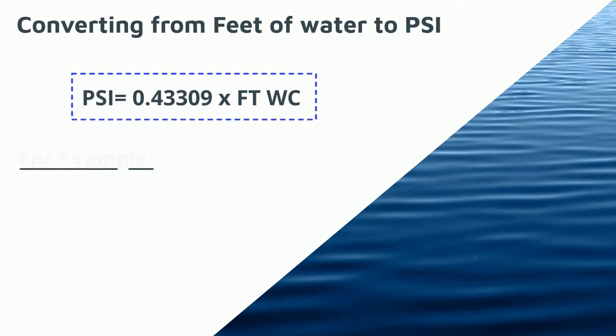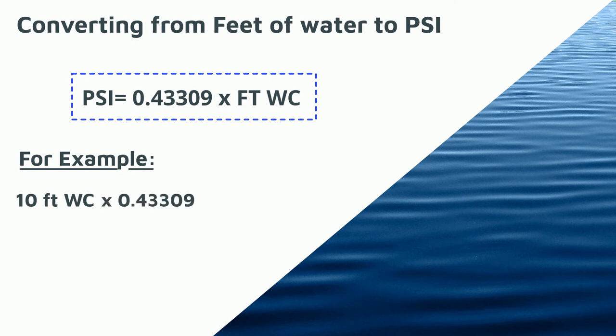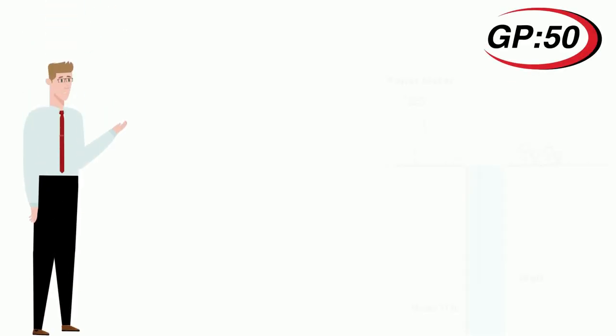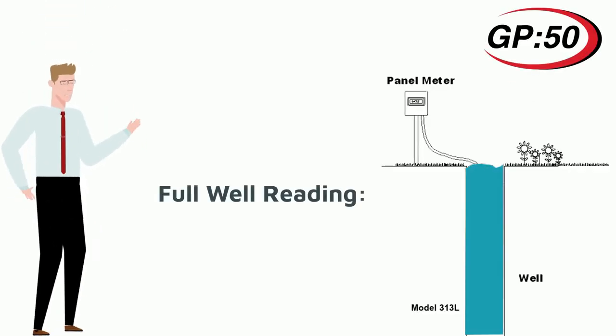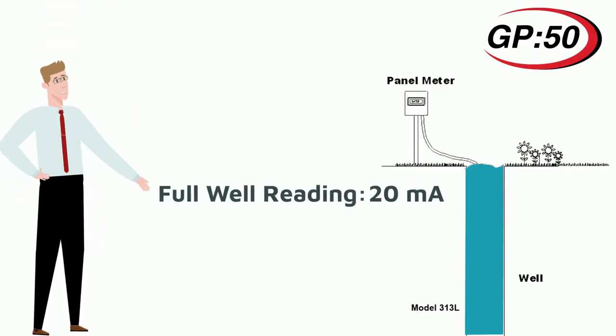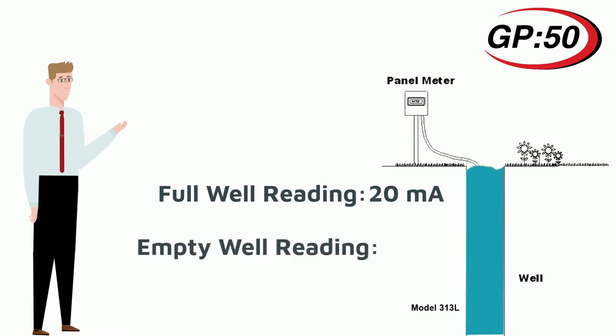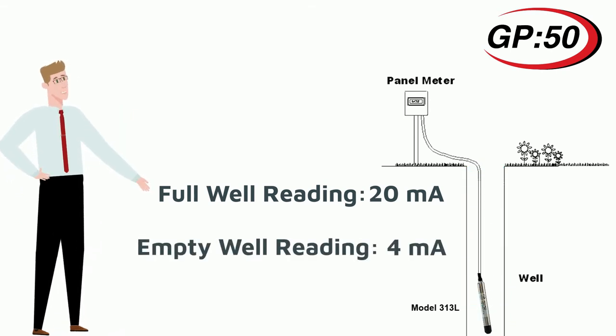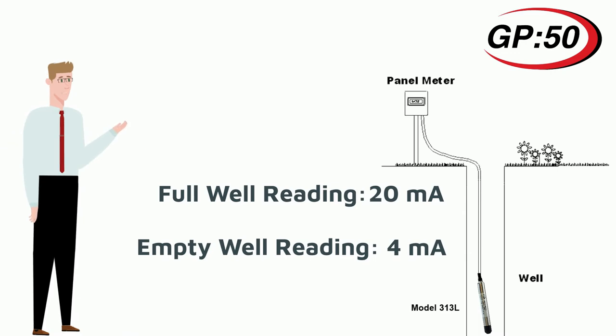For example, 10 feet of water column times 0.433 equals 4.33 psi. The level transmitter would have a calibrated range of 0 to 4.33 psi. When the well is full the unit reads 20 milliamps, and when the well is empty it reads at 4 milliamps, providing a linear reading at all the different depths of the water in the tank.